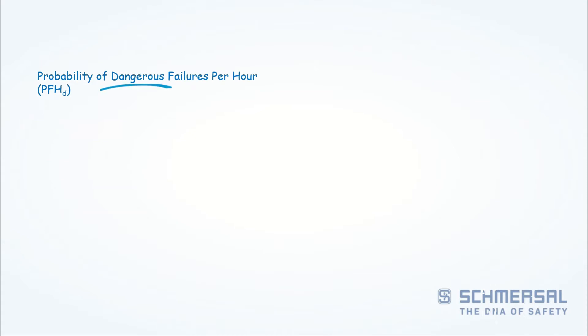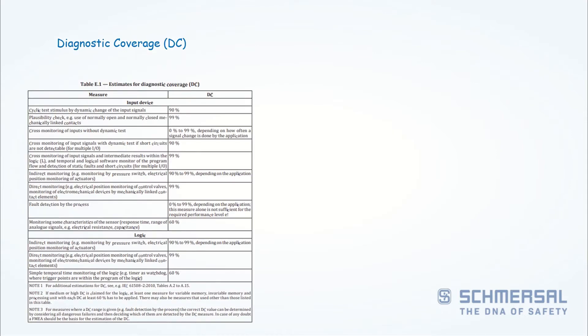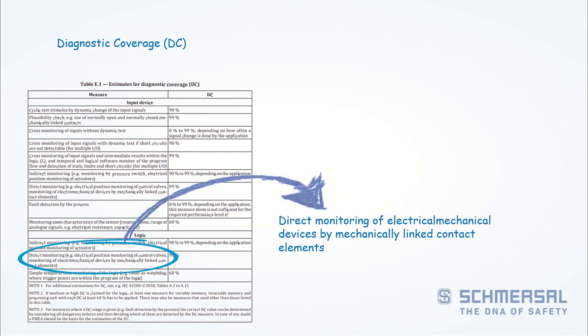These are the probability of dangerous failures per hour. In order to calculate your probability of dangerous failures per hour, ISO 13849 takes into account four parameters. This includes the diagnostic coverage, which essentially is the way we monitor our safety circuit.